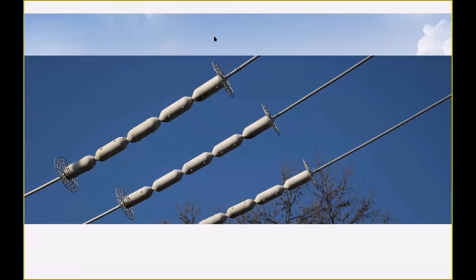The other thing you'll notice is that they're independent rollers, not just one roller, like a split piece of conduit 8 feet long, typically used for a guy guard. You could do that, but the problem with a single roller is that almost every line has a droop specification, for water runoff and other technical reasons we don't need to get into. But when the line droops with a single roller across it, it doesn't spin, the friction keeps it from spinning, which is not what you want.